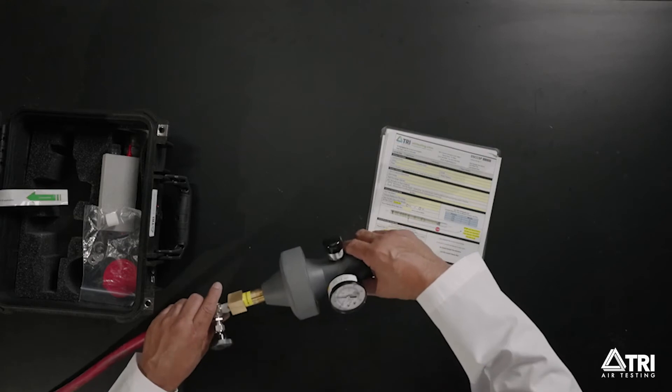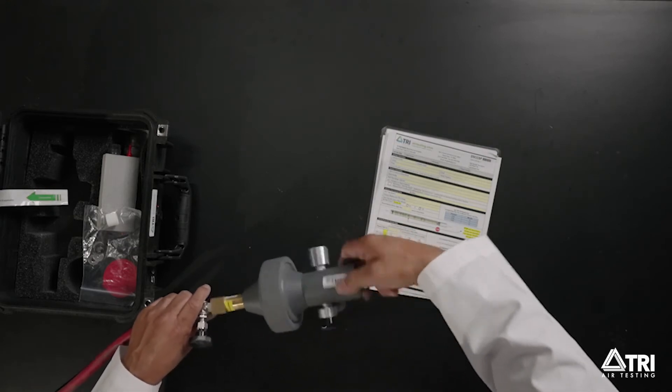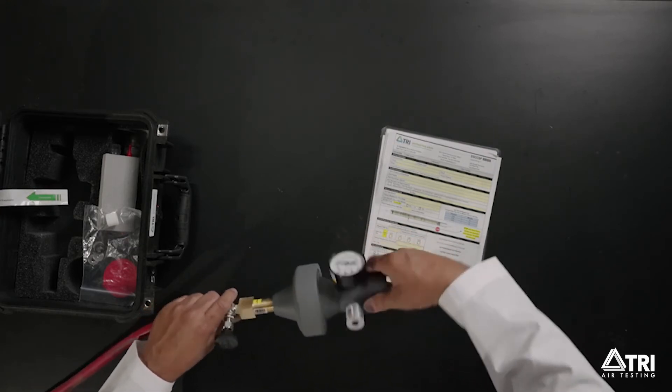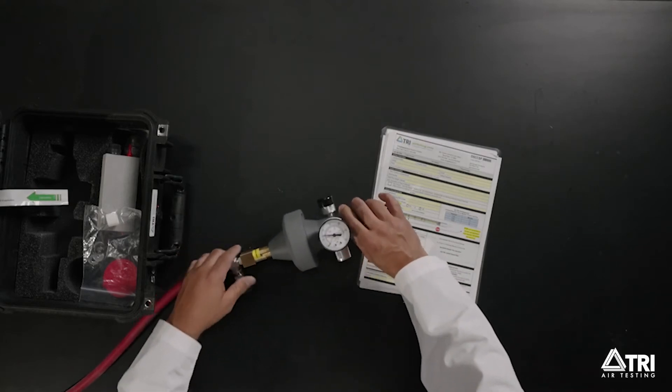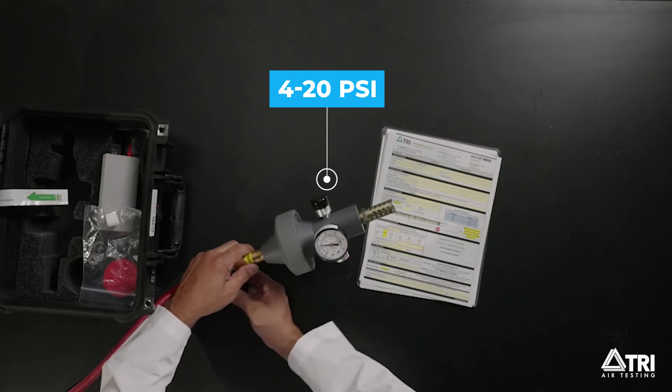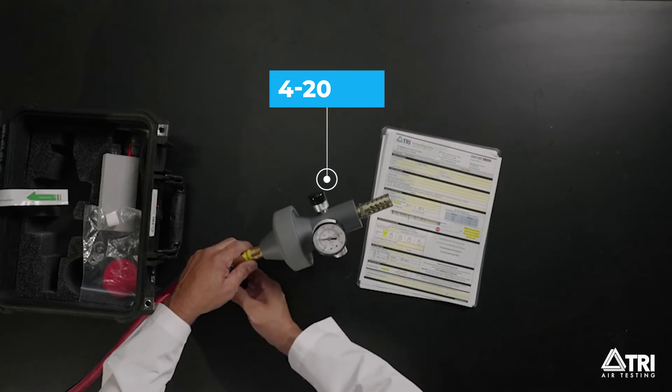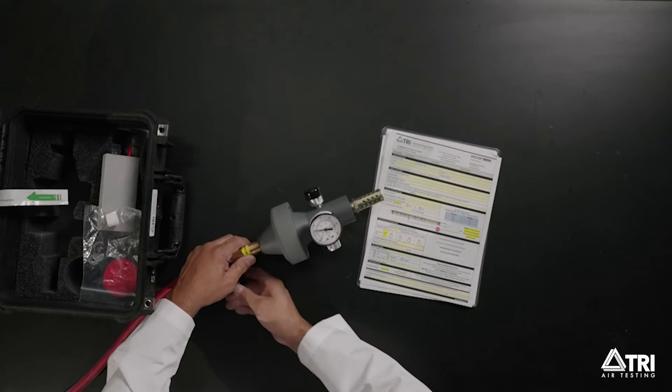Step 3. Connect the complete unit to your gas source. Open the gas source slowly and allow the pressure on the PVC flow section gauge to stabilize between 4 and 20 psi. You can adjust the psi with an inline valve to achieve the pressure. Do not allow the gauge to exceed 30 psi.